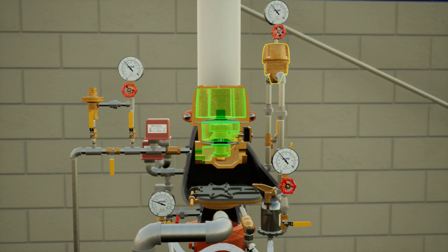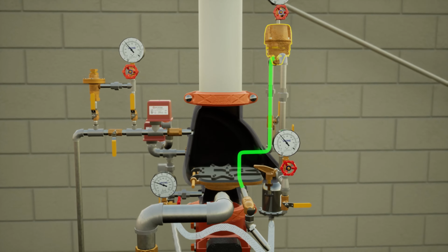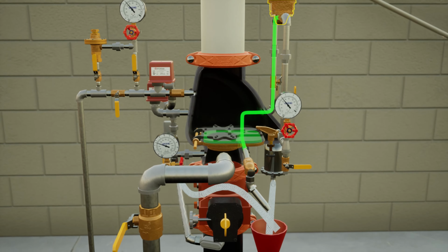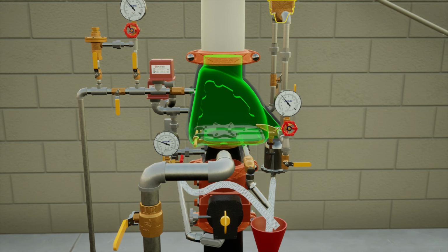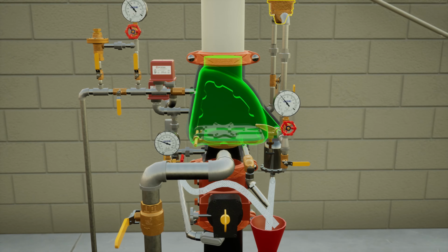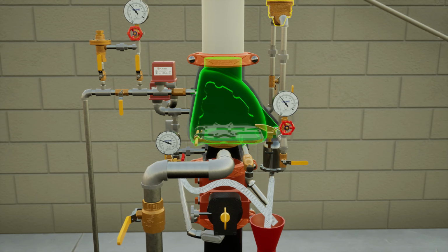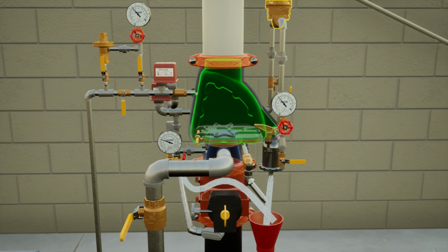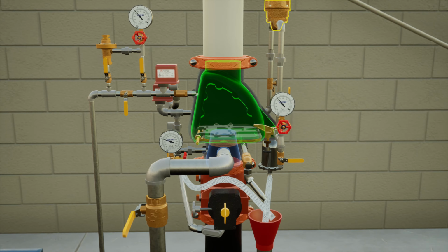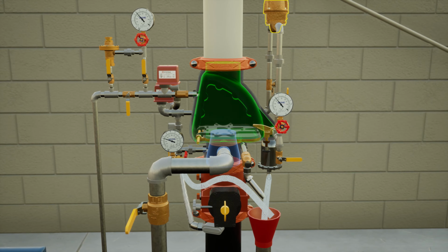A slight but sudden drop in air pressure from an activated sprinkler will cause the accelerator to activate, redirecting air to the intermediate chamber of the VXR valve. This adds pressure to the valve's intermediate chamber, causing the air differential between the outlet and the intermediate chamber of the VXR valve to equalize. This will allow the inlet water pressure to overcome the air pressure in the outlet as air pressure continues to drop due to the activated sprinkler.